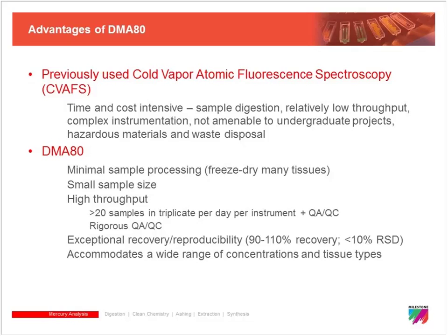The other thing that we really like about the DMA-80 is that it has exceptional recovery and reproducibility. When we're running certified standards, we're typically looking for between 90 and 110% recovery. That tells us that we're getting good, reliable results. But on the DMA-80, we usually do quite a bit better than that. We usually get between 95 and 105% recovery, and that's consistent over thousands of measurements. In addition, we usually have a relatively low relative standard deviation between triplicates, definitely below 10%, often below 5%. So we have a lot of confidence in the data we're getting from it.